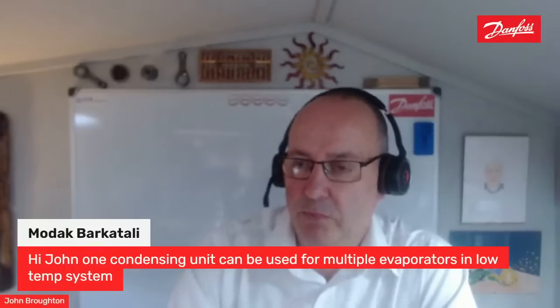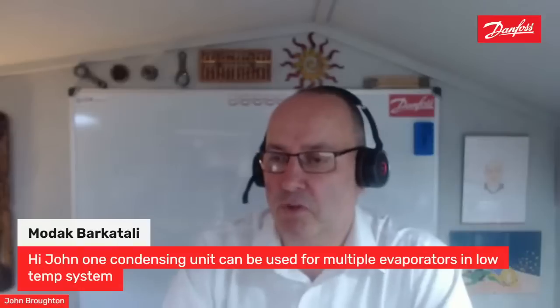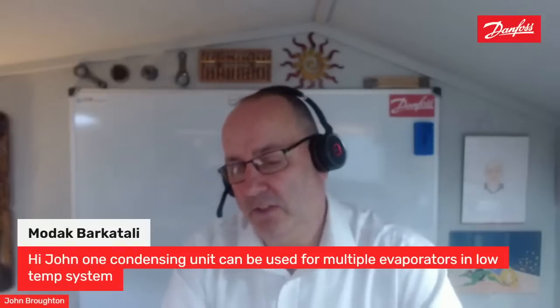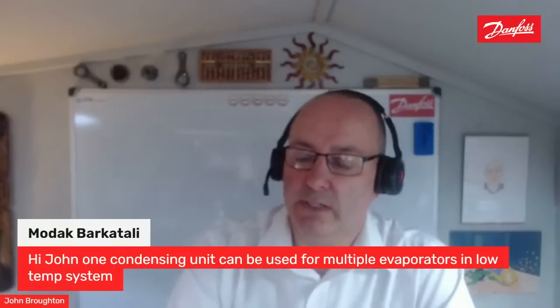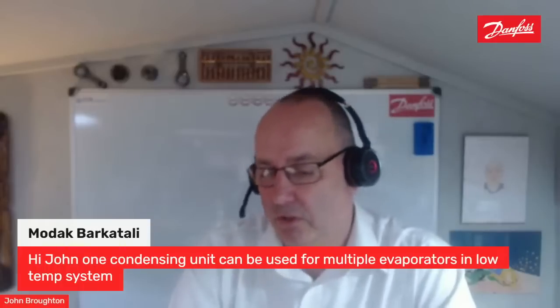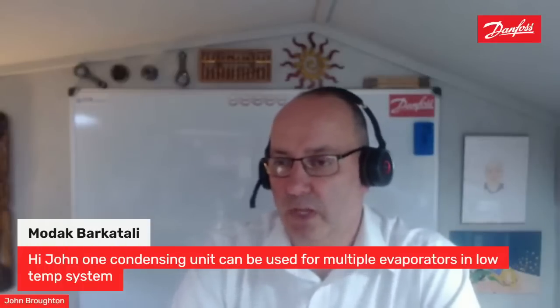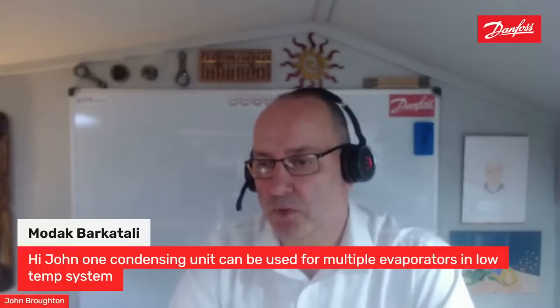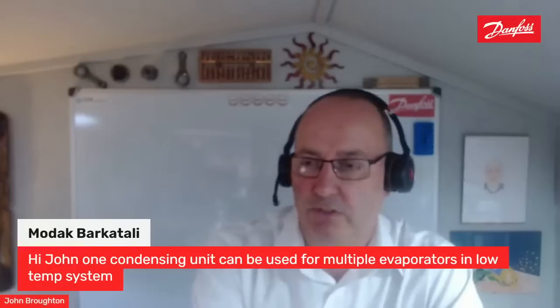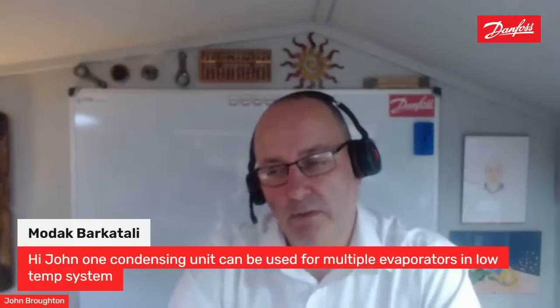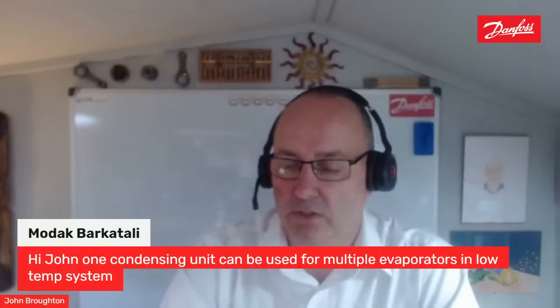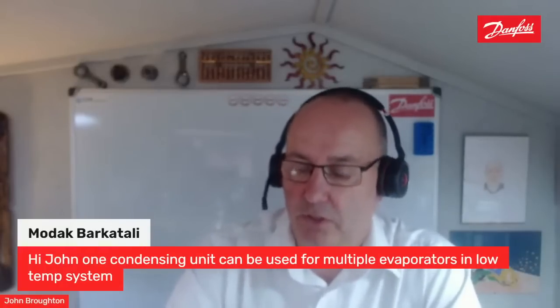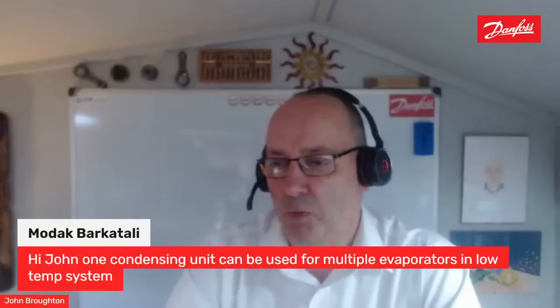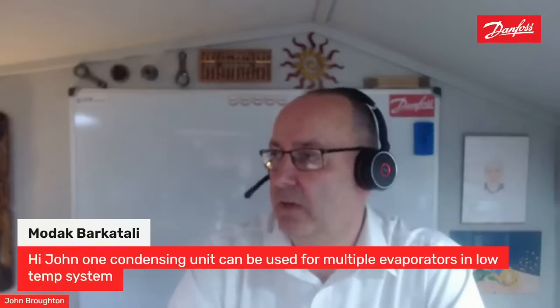If they're on separate thermostats, then you need some form of capacity control on that condensing unit to either speed up, slow down that compressor, or unload the cylinders, so that we have that capacity match between the condensing unit and the evaporators that are running. So yeah, it can be done, but you've got to look at the capacity control or how you are operating those evaporators.